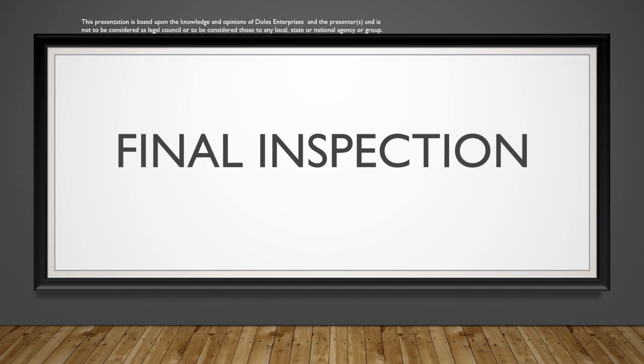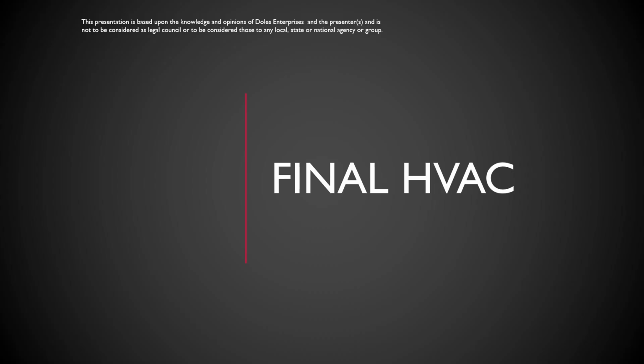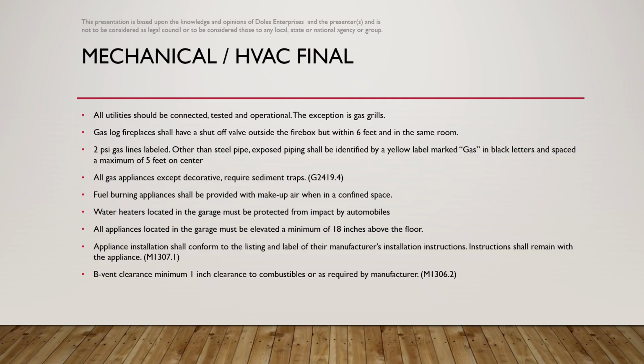The building final inspection process. Final inspection of the residential HVAC mechanical system. Final inspection issues include that all utilities should be connected, tested, and operational. The exception would be a gas grill. Gas log fireplaces shall have a shutoff valve outside the firebox, but within 6 feet and in the same room. 2 PSI gas lines shall be labeled. Other than steel pipe, exposed piping shall be identified by a yellow label marked gas in black letters and spaced a maximum of 5 feet on center.